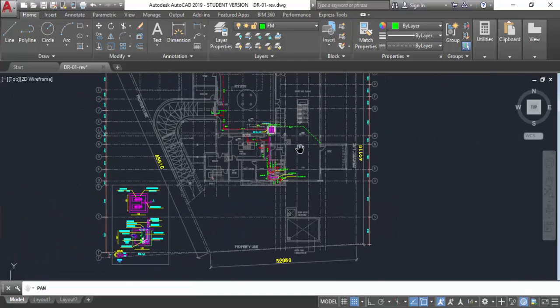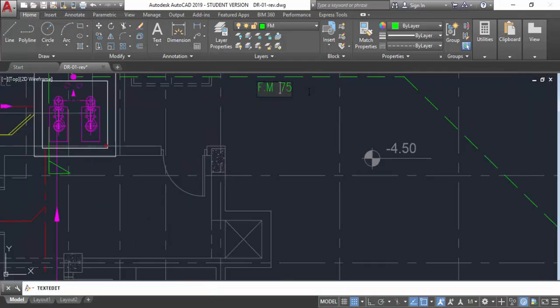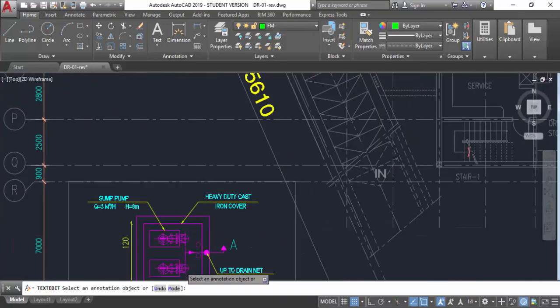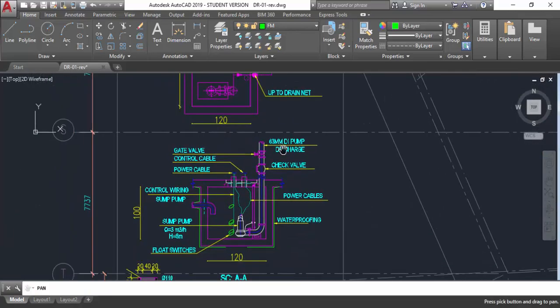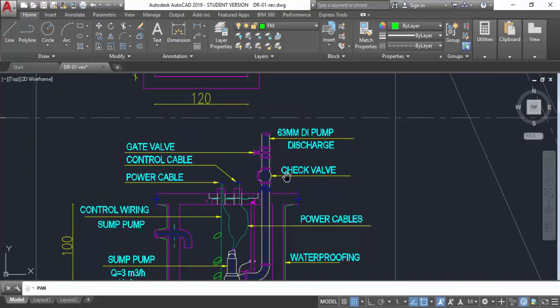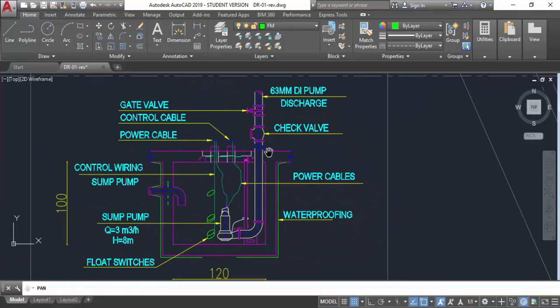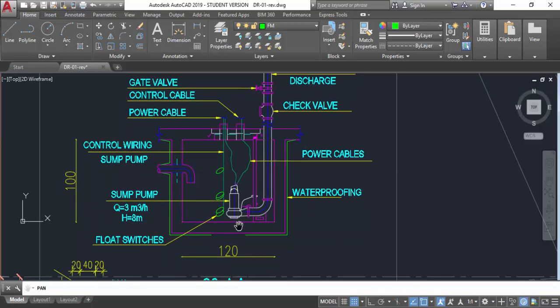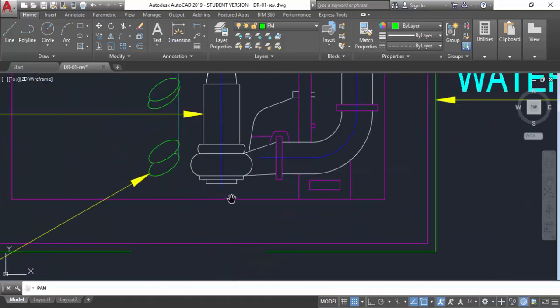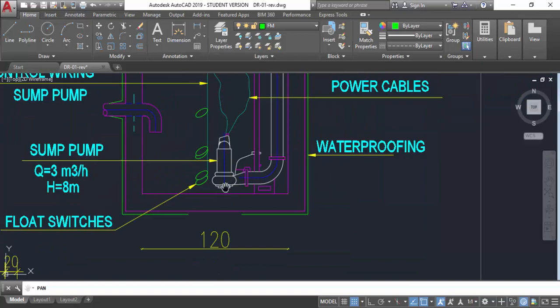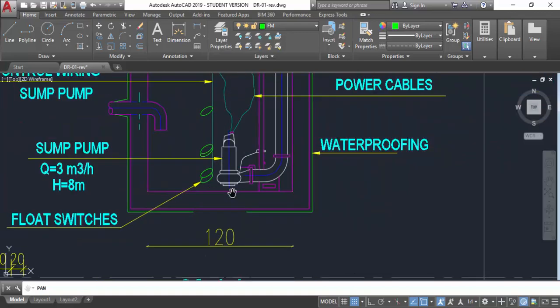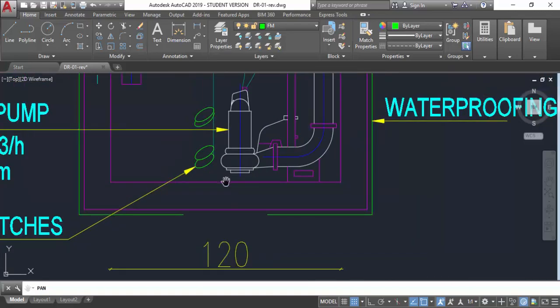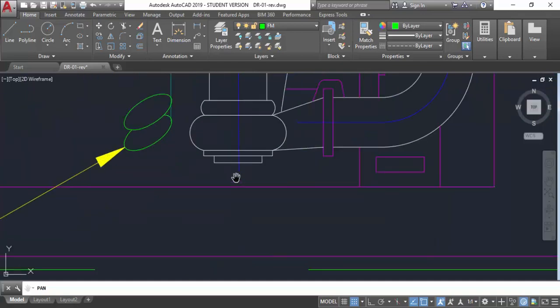We change the pipe diameter here to 65 mm. You can see in the section: the check valve is compulsory, meaning water will not come back. The check valve is required as per plumbing codes. You also have a gate valve for isolation and a discharge pipe going upward. There are two types of sump pumps: one without a grinder and one with a grinder. We use the grinder type when solids, garbage, or debris are coming in — the grinder will break them up and pump them out.